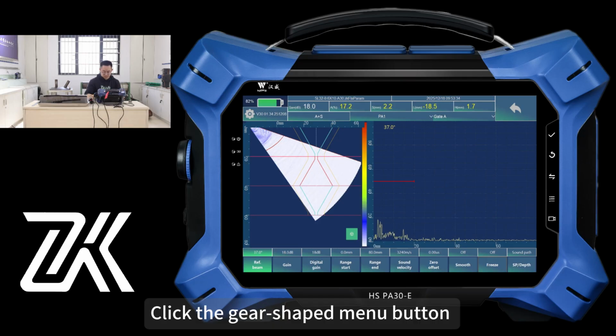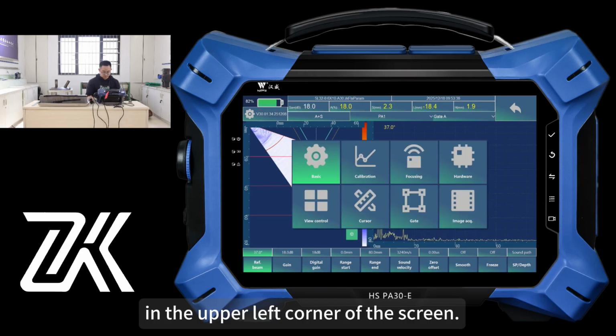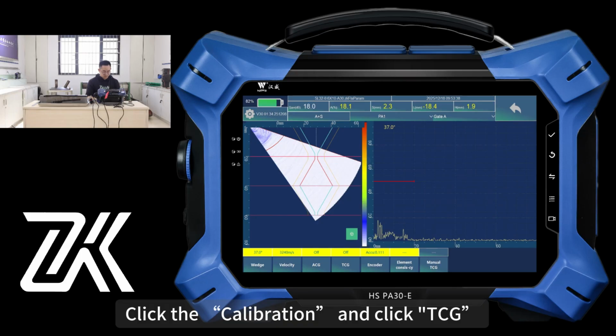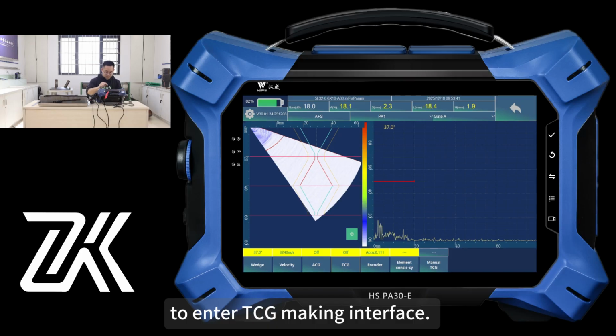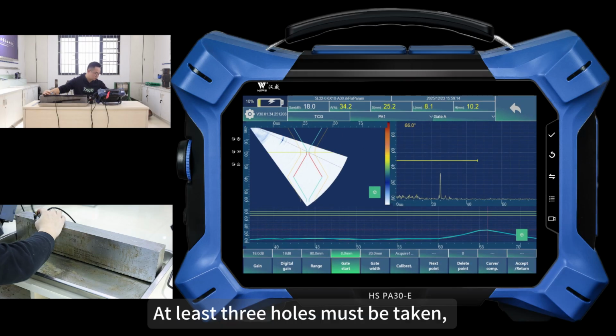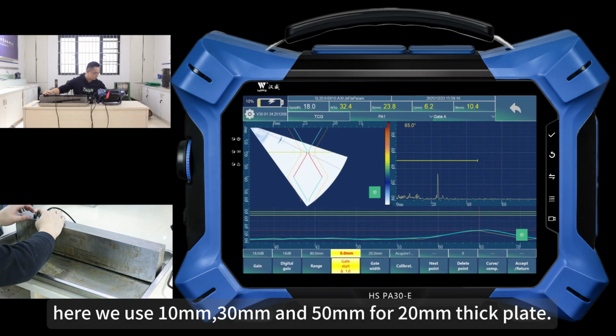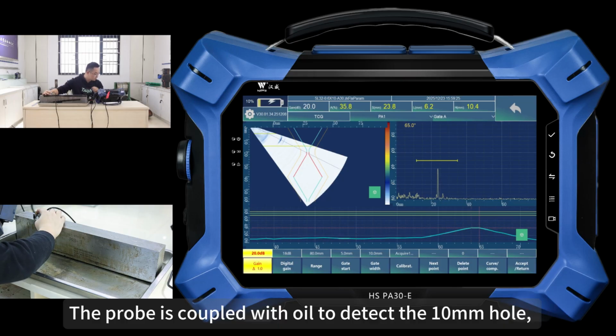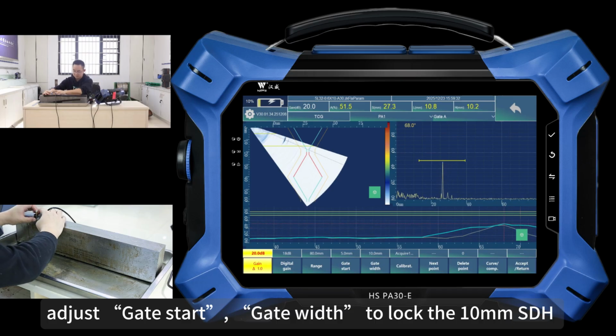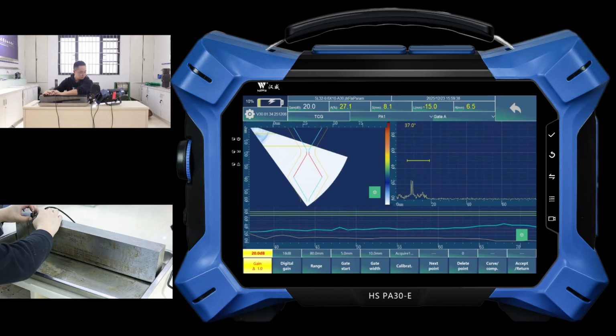Click the gear-shaped menu button in the upper left corner of the screen. Click Calibration and click TCG to enter the TCG making interface. At least 3 holes must be taken. Here, we use 10 mm, 30 mm, and 50 mm for the 20 mm thick plate. The probe is coupled with oil to detect the 10 mm hole. Adjust gate start and gate width to lock the 10 mm SDH and adjust gain value.